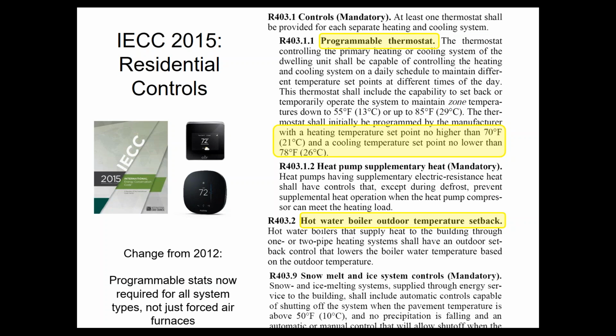Really, the only big change on here from the 2012 version is that there used to be an exception for radiant floor systems to not have to use a programmable stat. The radiant floor system has a 6-hour, 8-hour lag time, so a programmable stat doesn't make sense. That exception is gone, so technically you have to have a programmable stat even on a radiant floor, although I would argue it doesn't make sense, but that's the way the code's written.